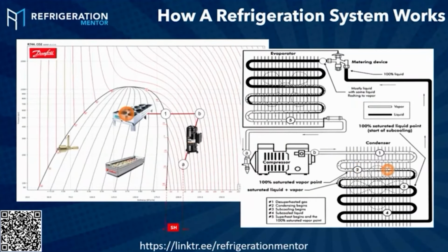We hit this condenser. It has air flow through it. It has heat going through it. So as that air goes through it, it's actually cooler air going through it, to drop that temperature to start to condense it. So when we get to the outlet, liquid line, drop leg, people will call it, depending on your condensation line, there's lots of different terms.